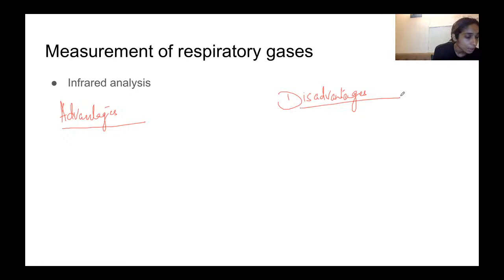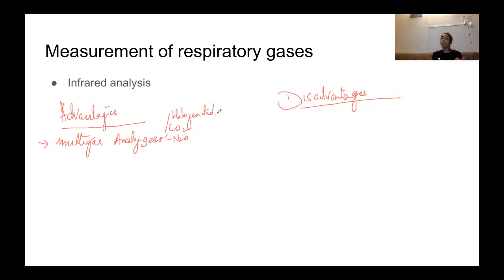So basically, your advantages are, infrared analyzers are multi-gas analyzers. They are capable of measuring carbon dioxide, nitrous oxide, and all of the commonly used potent volatile anesthetics. So basically, your carbon dioxide, nitrous oxide, and your halogenated agents. Basically, your inhaled anesthetics, but it cannot measure non-polar gases such as oxygen, xenon, helium, nitrogen. Right? Remember that. Then volatile agent detection, it is able to detect the particular volatile agent.